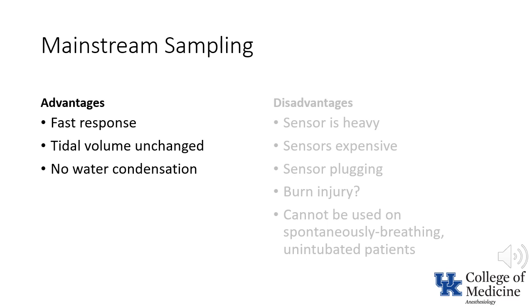Mainstream sampling provides a faster response. Other advantages include an unchanged tidal volume. With sidestream capnometry, the monitor aspirates gas from the circuit and transports it to the site of measurement, which obviously results in a reduction in delivered tidal volume.